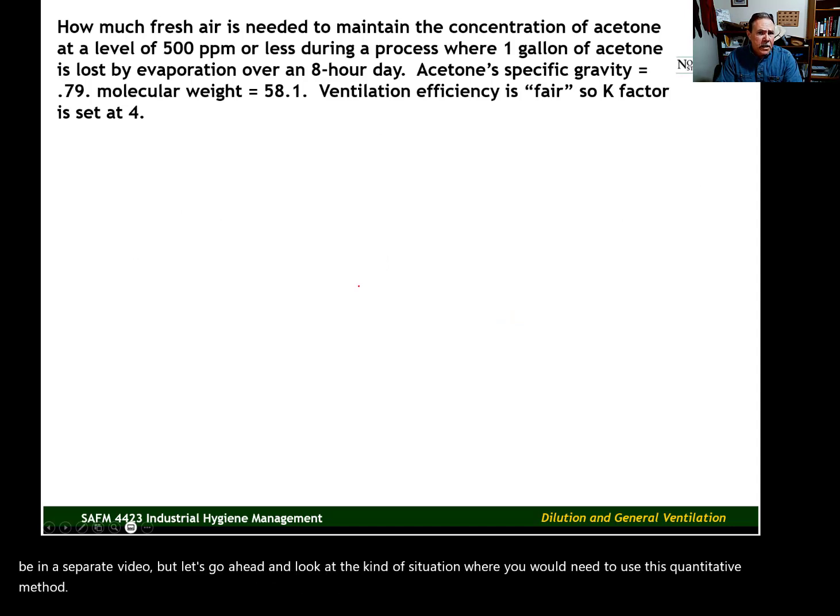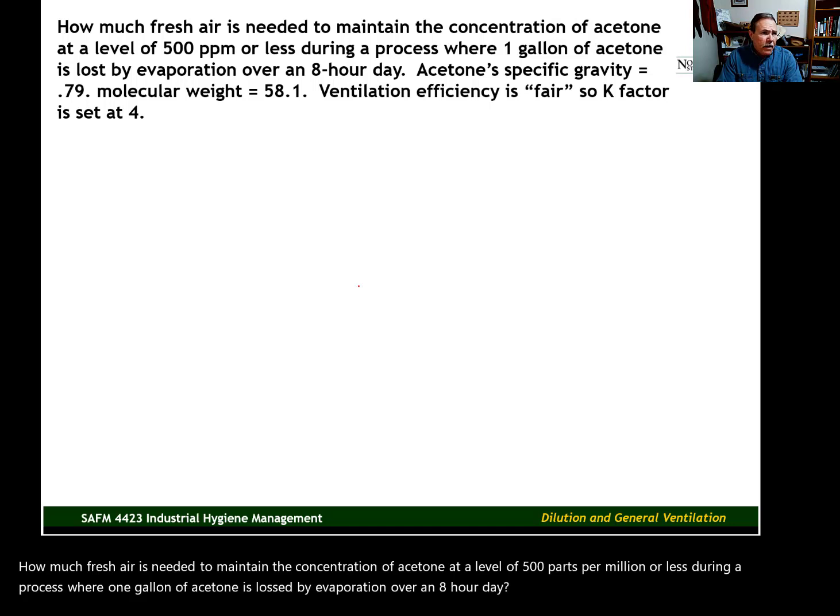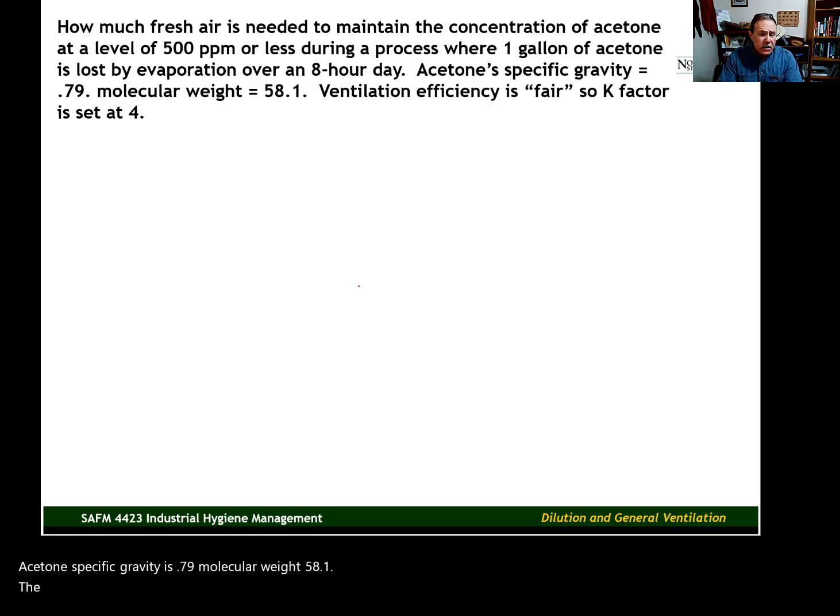How much fresh air is needed to maintain the concentration of acetone at a level of 500 parts per million or less during a process where one gallon of acetone is lost by evaporation over an eight hour day. Acetone's specific gravity is 0.79, molecular weight 58.1. The ventilation efficiency is considered fair, so the K factor is set at four.